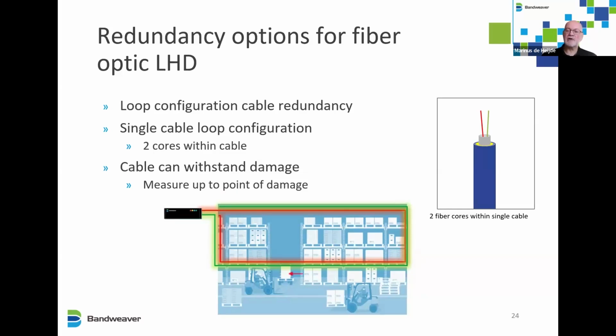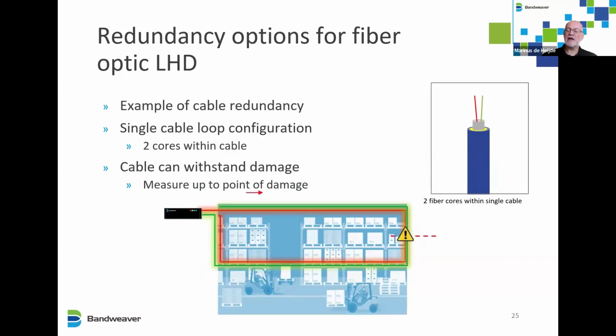So I'll show that here. The red fiber will start at channel 1, but will terminate just before channel 2. So the laser goes through it like that. And then the green cable will come out of channel 2, go back and terminate just before channel 1. Now, if we get a cable cut, the laser will still go through the red fiber and the green fiber up to the cut. If there is a cut, you will get an alarm and a fault with the location, so you can then go and repair the cable.